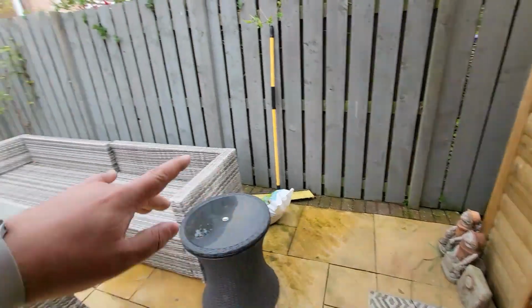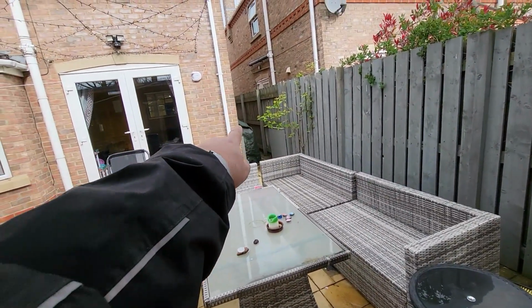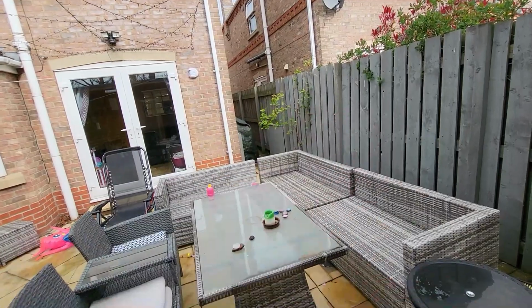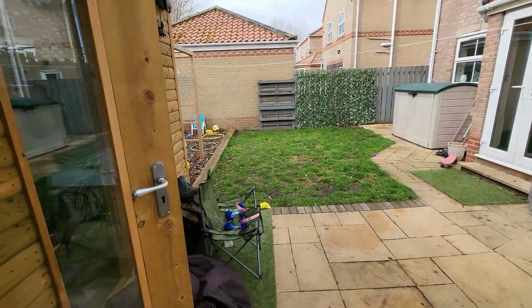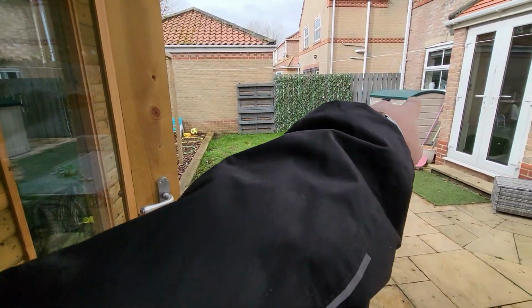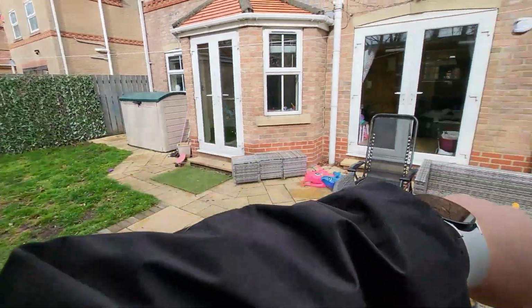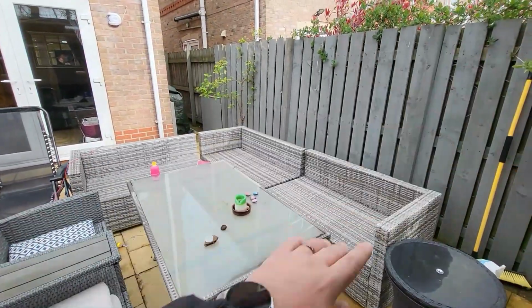And even on the 10-meter distance, where our electrode is to where the main earthing terminal is, it's not 10 meters. It's very difficult in this garden to get 10 meters away from that in any case, because next door's is just here and the other side is on the other side of the house over there as well. So it's even more tricky in other urban areas where you've got terraced housing and back-to-back, and you could even have rows of houses supplied off different transformers but sharing water bonds. It gets really, really complicated.